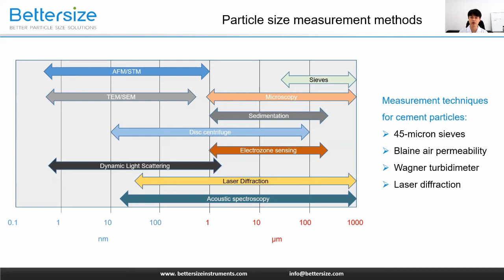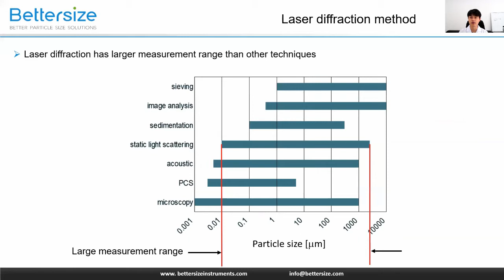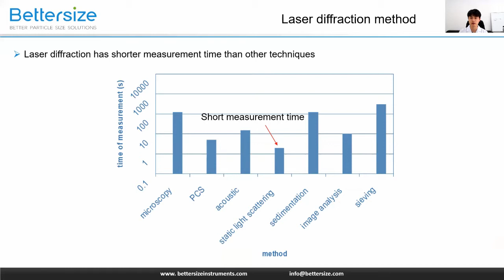Compared with other measurement methods, what are the advantages of laser diffraction? In this picture, static light scattering or laser scattering has a wide range, covering most of the particle size distribution of powder particles. Theoretically, it can measure particles from 10 nanometers to several microns. The single measurement time of laser diffraction is very short. Every measurement of the microscope, sedimentation, and sieving methods that you may be familiar with takes at least several minutes. But if you use laser diffraction, you can get a test result in a few seconds. In terms of measurement speed and convenience, laser diffraction has great advantages.